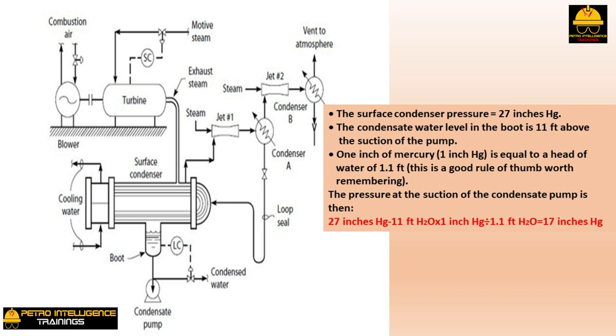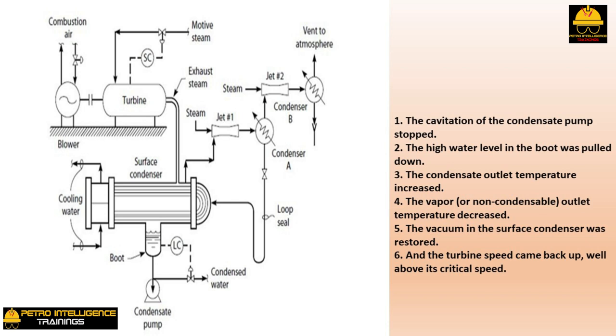To stop the suspected air leak, water was sprayed from a hose over the pump seal. Instead of sucking air, the leaking seal drew in cold water. As a result: (1) cavitation of the condensate pump stopped; (2) the high water level in the boot was pulled down; (3) condensate outlet temperature increased; (4) the vapor/non-condensable outlet temperature decreased; (5) vacuum in the surface condenser was restored; and (6) turbine speed came back up well above its critical speed — but not for long.